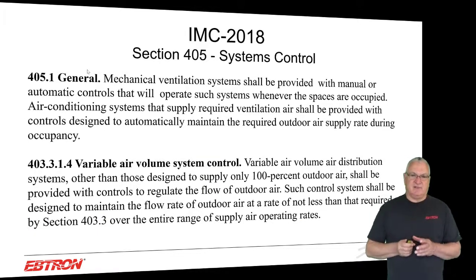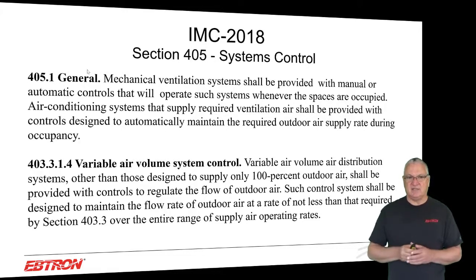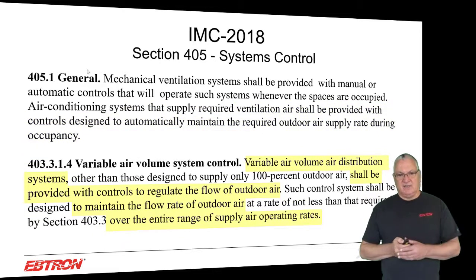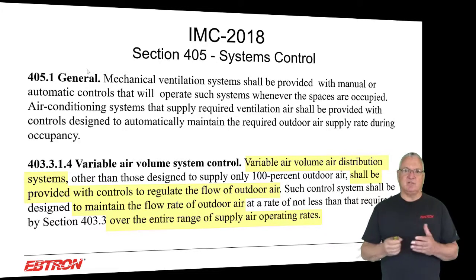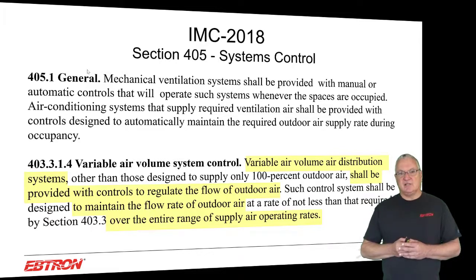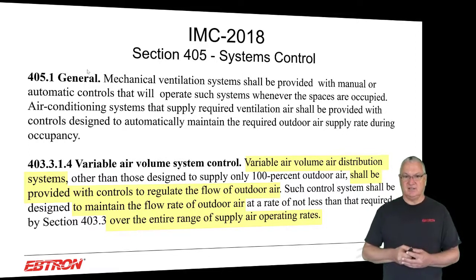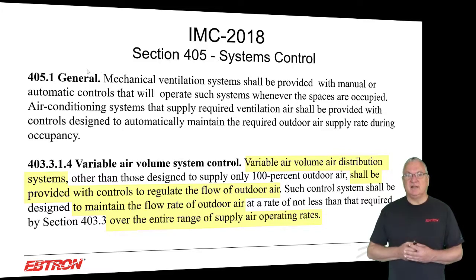The IMC also shows how close it is to Standard 62. Ventilation air shall be provided with controls designed to automatically maintain the required outdoor air supply rate during occupancy. The IMC's variable air volume system control section — which will obviously need to be modified now to include multi-speed constant volume — states: variable air volume air distribution systems shall be provided with controls to regulate the flow of outdoor air to maintain the flow rate over the entire range of supply air operating rates. That's essentially identical to Standard 62, except it doesn't yet say multi-speed constant volume.